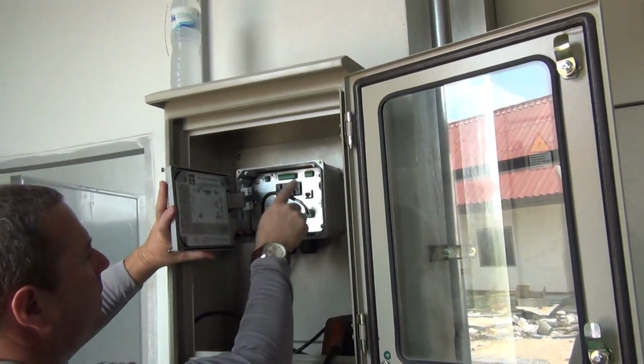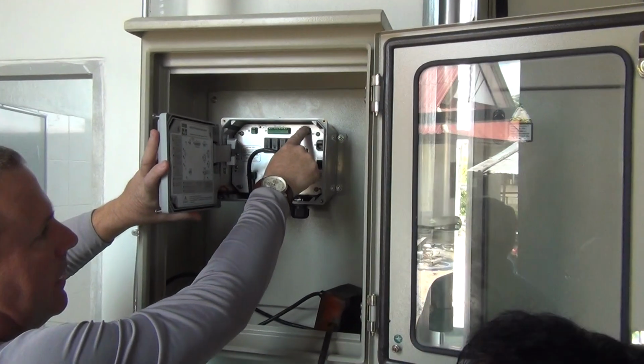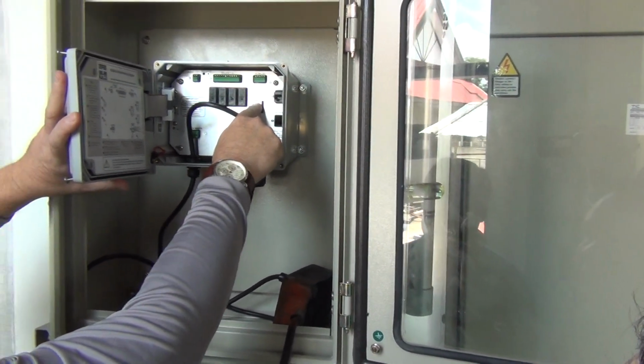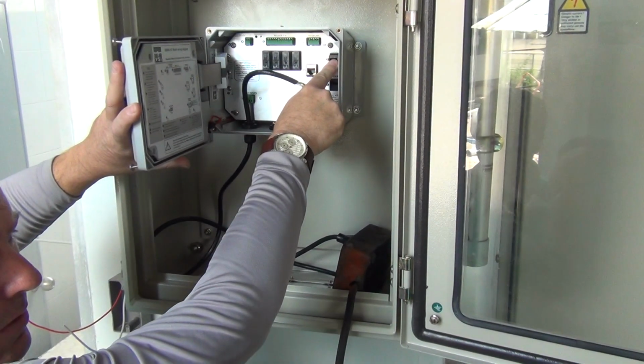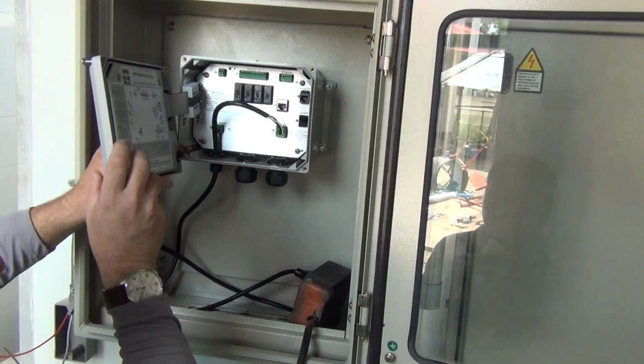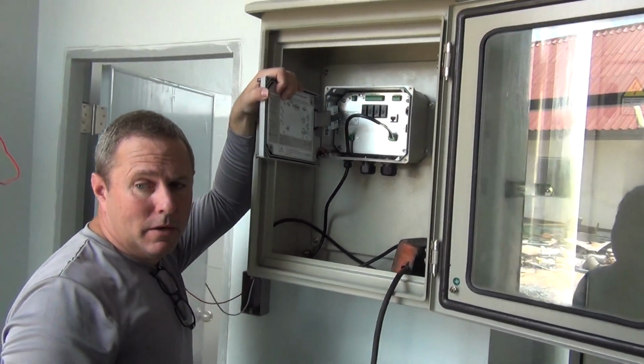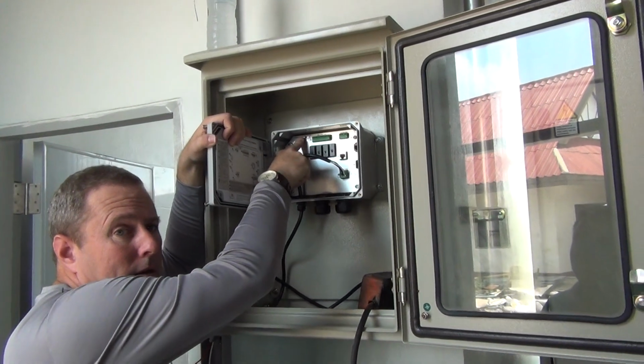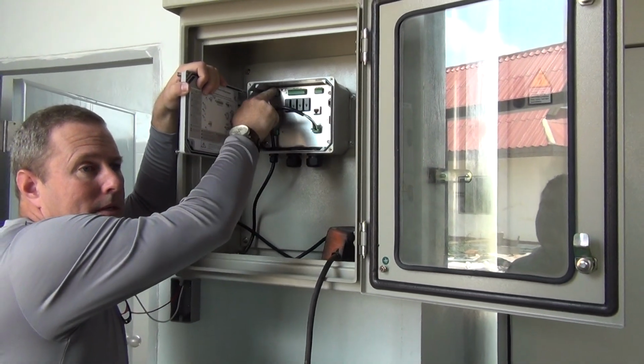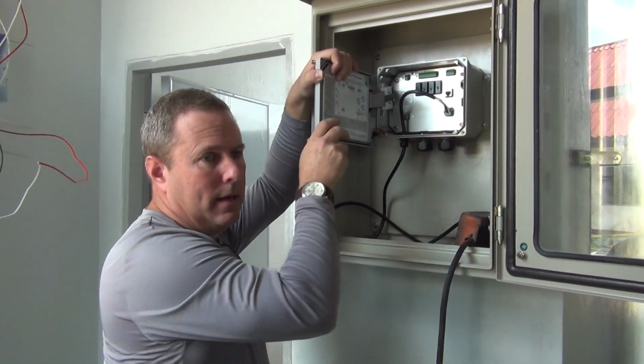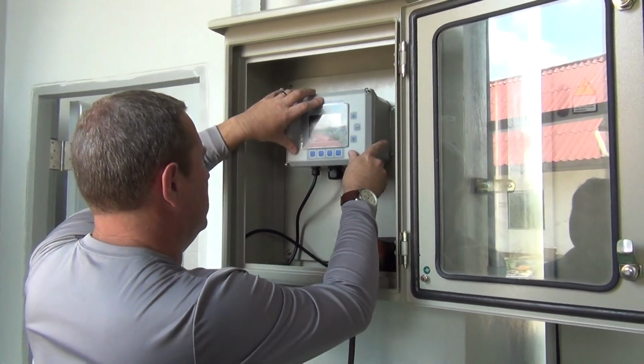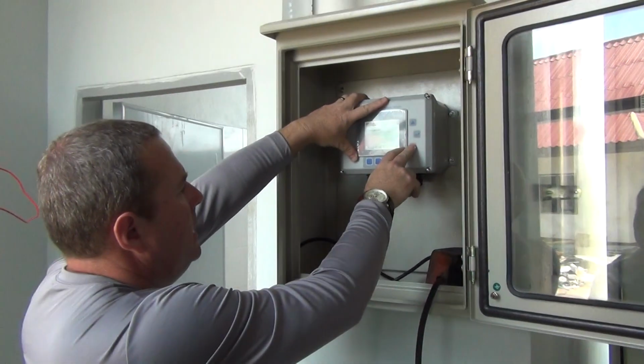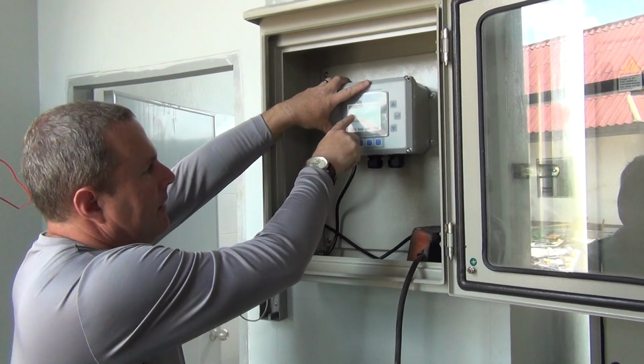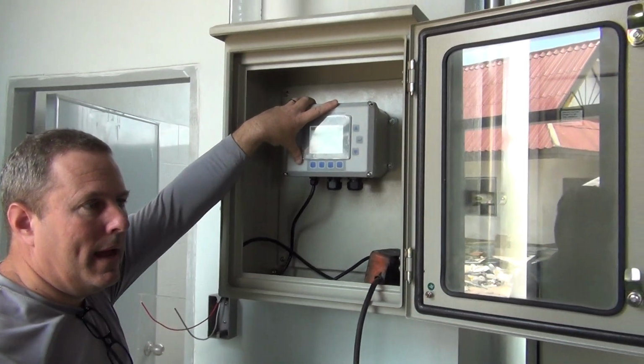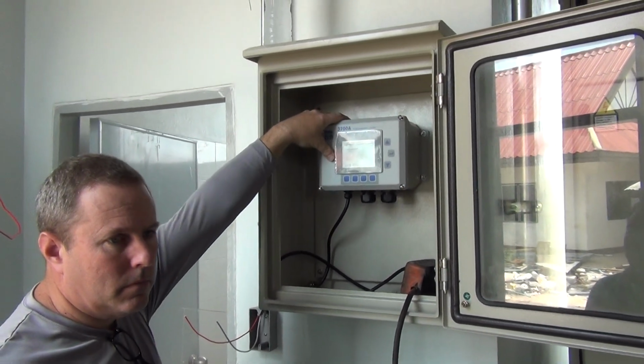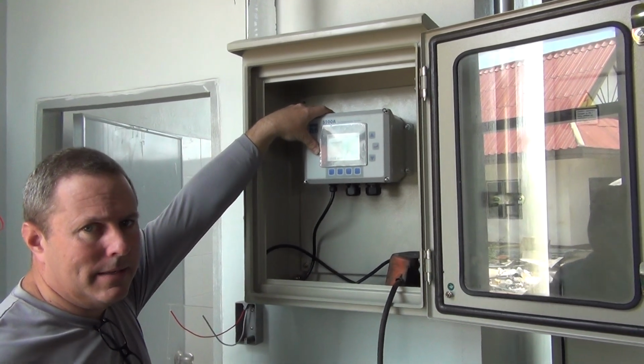The physical interface, this is the RS-485, right here where my finger is. And then this would be the connection for the RS-232. And then, of course, here is for the internet and Ethernet. Okay? Now, if you want battery backup in the event of power failure, you can run 12 volt DC here. And then if you lose the AC power, it would stay running on the DC power. Okay? Okay. So, communications under here, we have, if we want to run the 485, you have to determine if this would be a master or a slave, and whether it's going to have terminating power or not. If I'm going too fast, please tell me if anything is not clear.